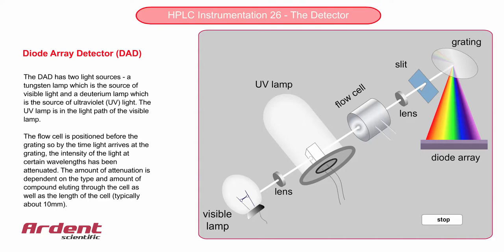The transmitted wavelengths fall on an array of diodes, and each diode will receive a certain wavelength band of light. The total peak response is the total response from the light which is hitting all the diodes.